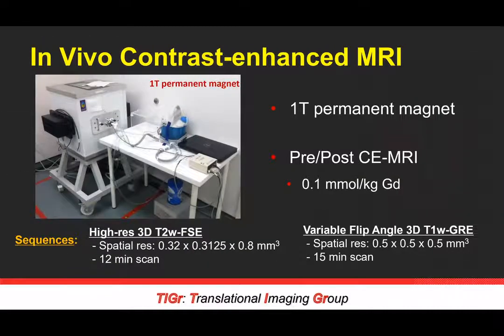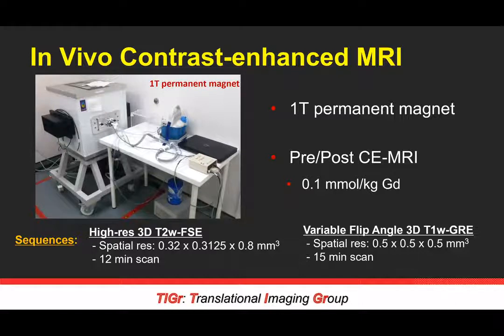This is a murine research model using a pregnant mouse model and 1 Tesla permanent magnets developed by ASPECT. The 1 Tesla permanent magnet is a useful system. You can see the setup on screen with a circulating water bath to keep the animal warm, an isoflurane absorber to prevent exposure to the user, and respiratory and cardiac gating. The magnet itself is on the far left, and the convenience of having a permanent magnet with electronics just nearby makes it a very nice system.